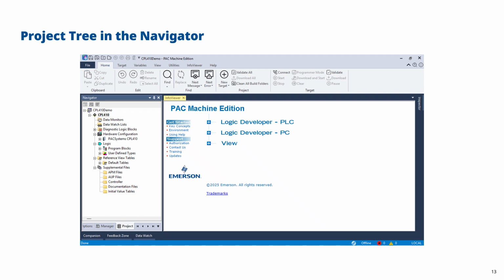You've then got various documentation files and controller details. The idea of the controller is that if you put a file into there, you can double click it and open it up. If you put a file into that controller location, it will be downloaded as a supplemental file into the controller memory. So inside the CPU, when we download, it stores all your comments, including things like variable names, variable descriptions, rung comments, but also anything in that controller folder.